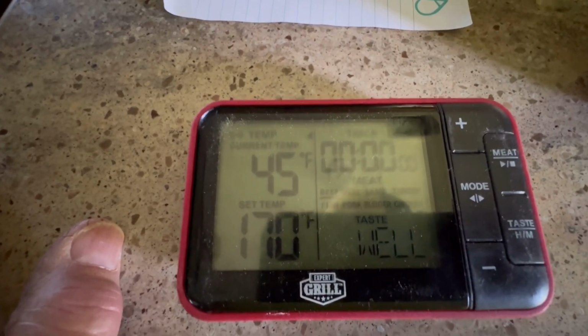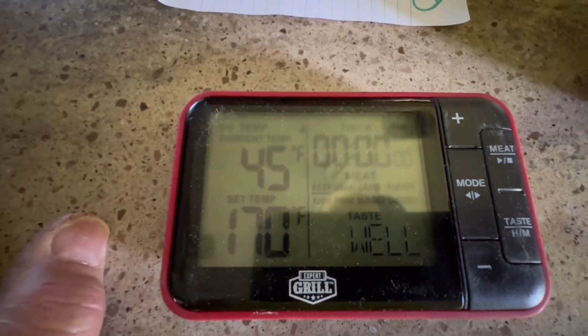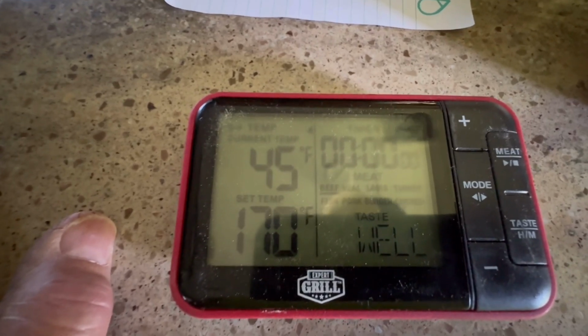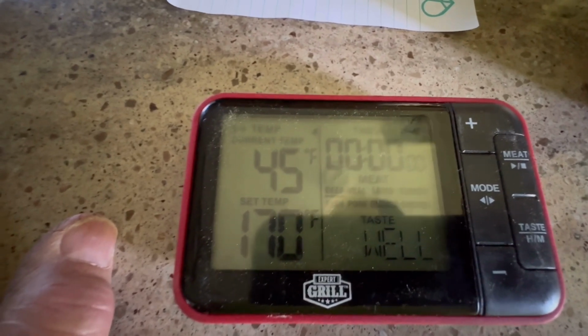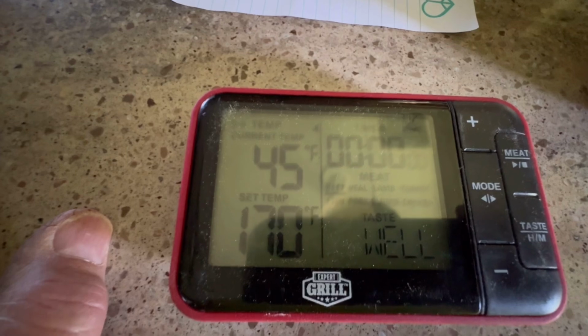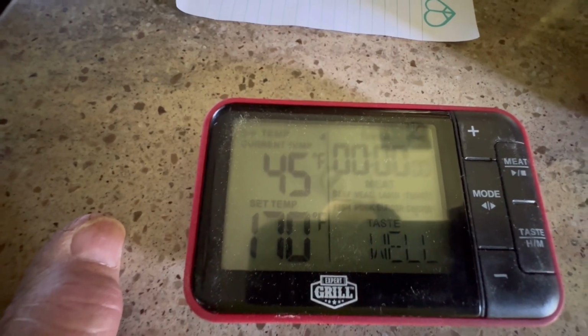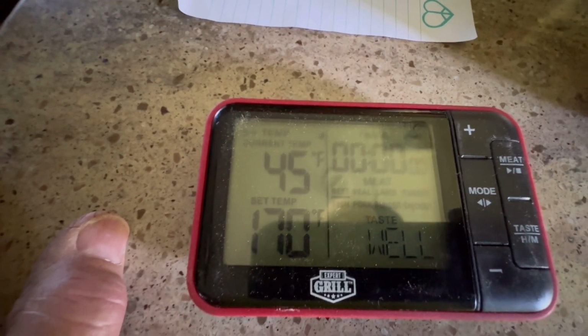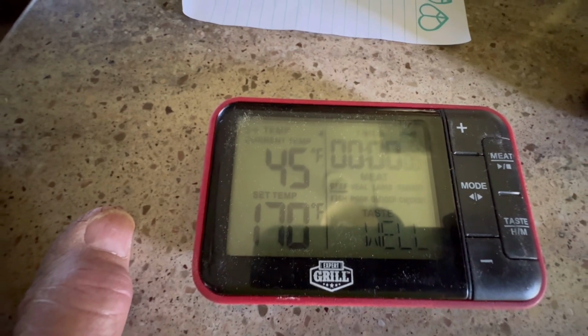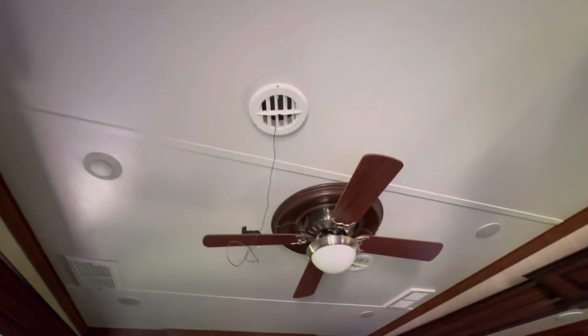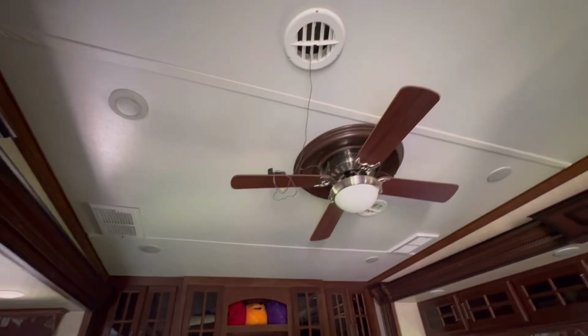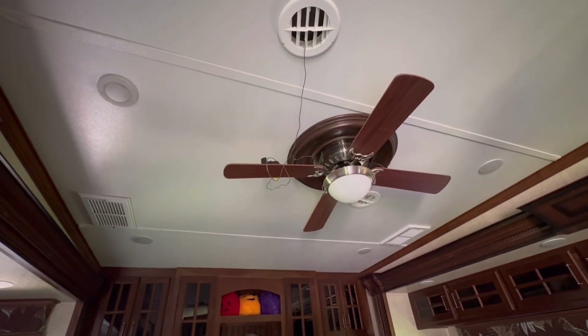Since I'm an old fart, I had to pause the camera for a minute and really think about that. But that looks to me like about 27 degrees differential between the return air and the output duct air. So we had 72 at the return and 45 coming out of the overhead duct on the Brisk Air 2 unit that's now 12 years old. So I would say that unit's working very good.